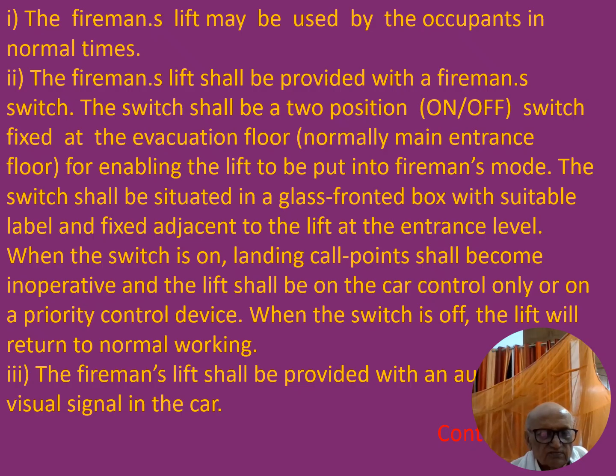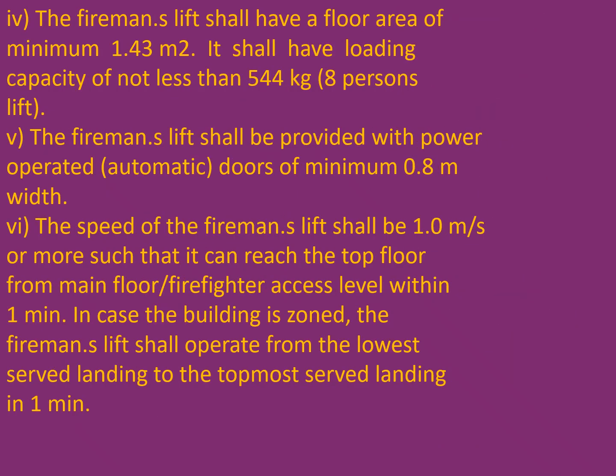The fireman lift shall be provided with an audio visual signal in the car. To be continued. The fireman lift car shall have a floor area of minimum 1.43 square meter. It shall have a loading capacity of not less than 544 kg, that is equivalent to 8 persons lift in India. In India, an average person is taken as 68 kg. The fireman lift shall be provided with power operated doors of minimum 0.8 meter width.